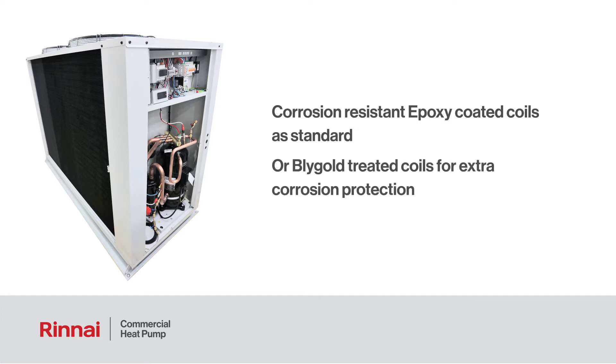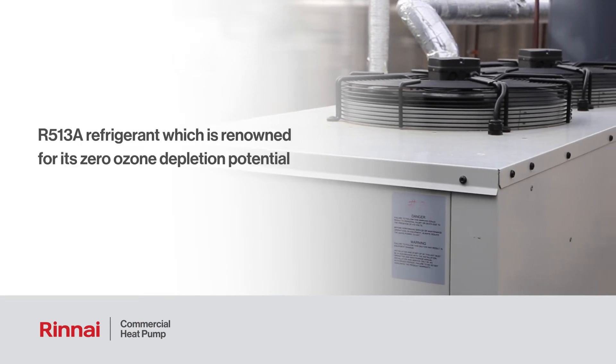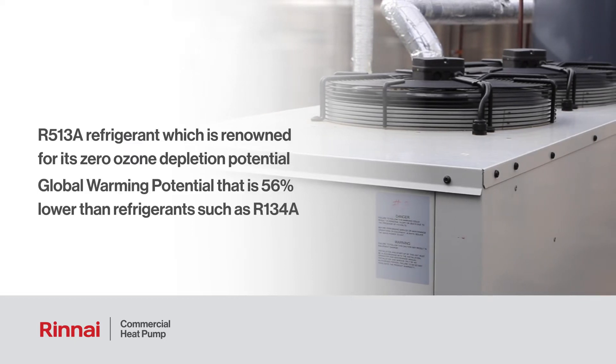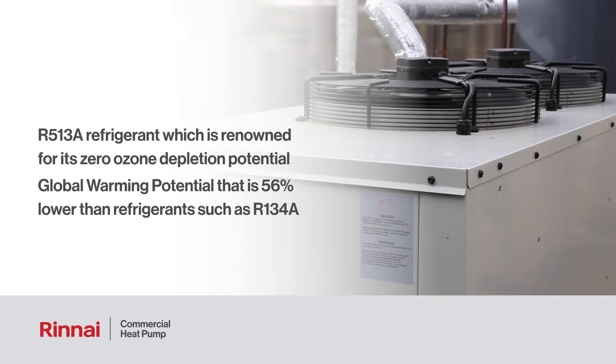Or you can choose Blygold treated coils for extra corrosion protection — one of many customizable options to suit your needs. The heat pump uses the revolutionary R513A refrigerant, which is renowned for its zero ozone depletion potential and for having a global warming potential that is 56 percent lower than refrigerants such as R134A, which is traditionally used in these applications.